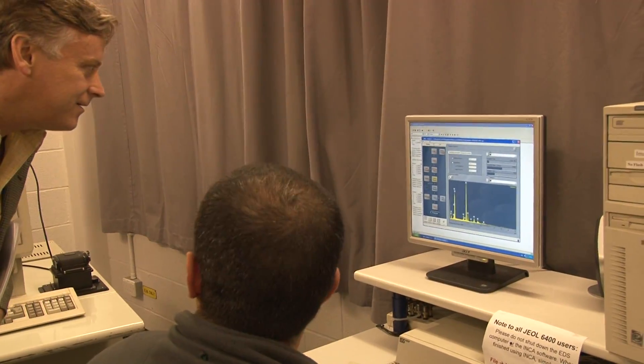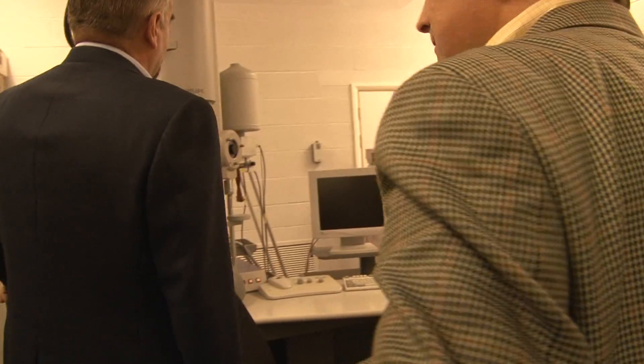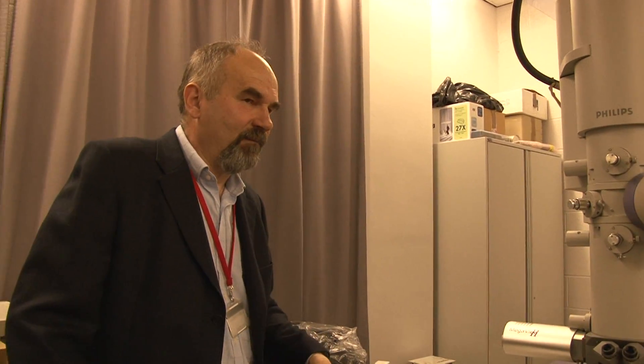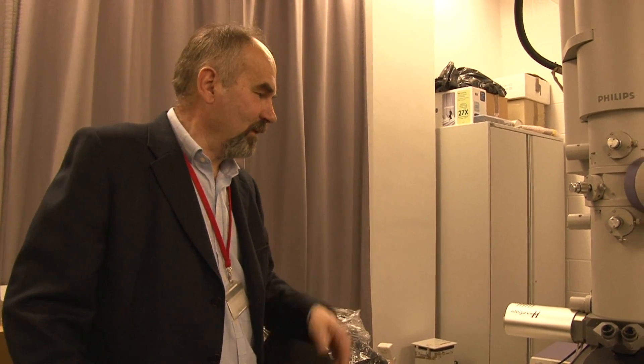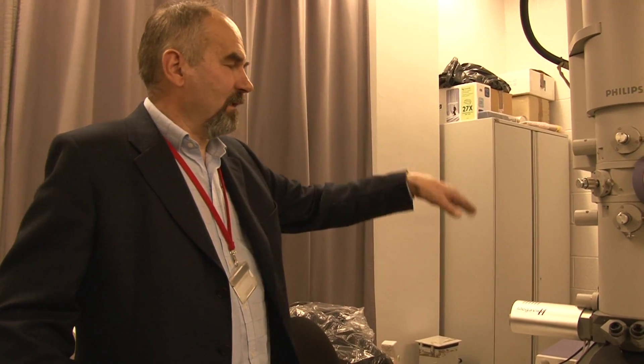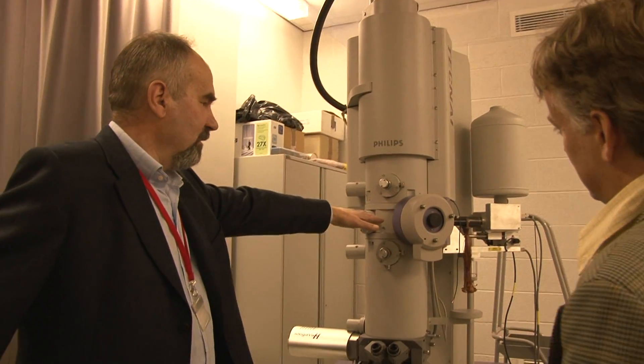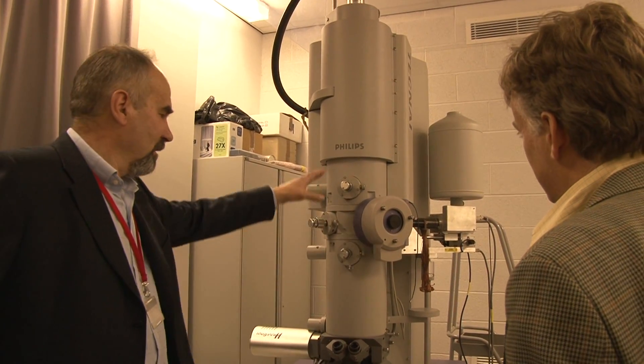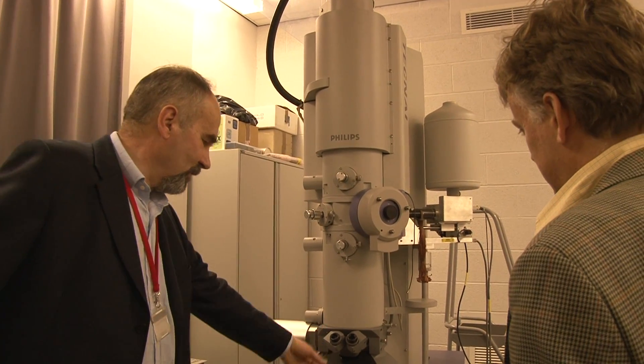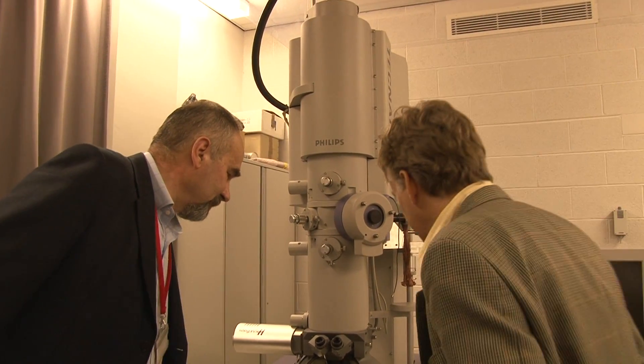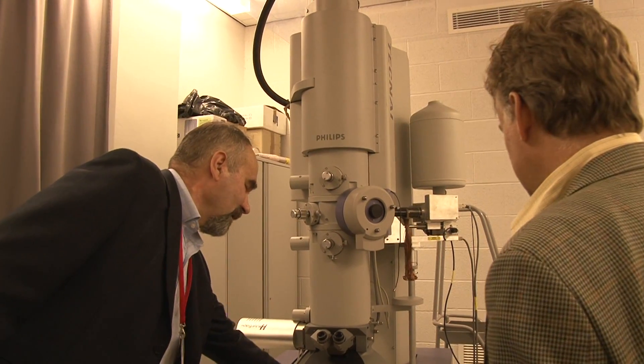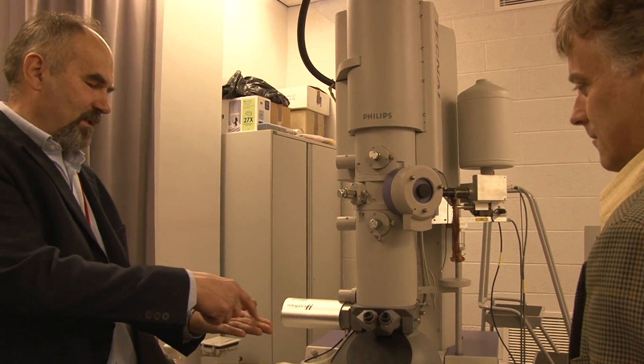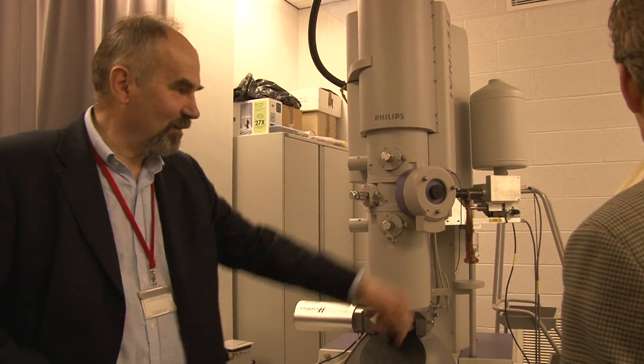This is just the sort of thing we need. This is a 200 kV transmission electron microscope — we've got two others at 300 kV accelerated voltage. The difference is that in a scanning electron microscope you put the sample at this level and process the signals emitted from the sample, whereas in this case you use electromagnetic lenses to produce the image on a fluorescent screen or camera. The sample is normally stationary; in scanning microscopy you move the beam across the sample.